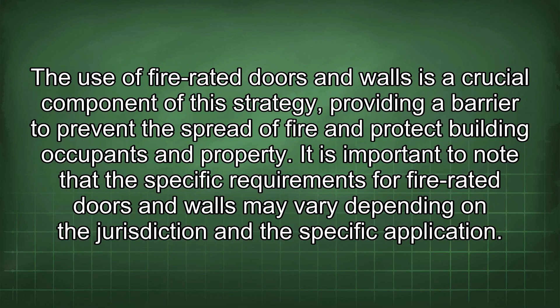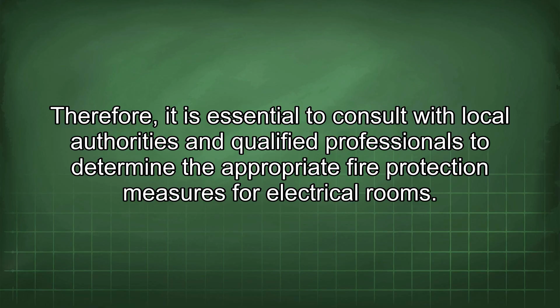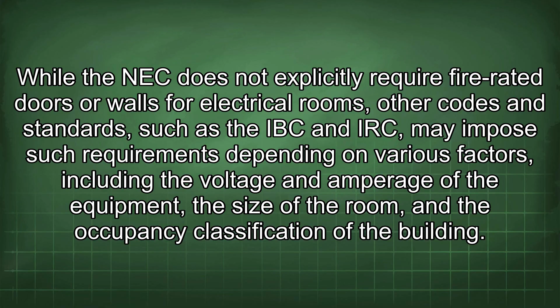It is important to note that the specific requirements for fire-rated doors and walls may vary depending on the jurisdiction and the specific application. Therefore, it is essential to consult with local authorities and qualified professionals to determine the appropriate fire protection measures for electrical rooms. While the NEC does not explicitly require fire-rated doors or walls for electrical rooms, other codes and standards such as the IBC and IRC may impose such requirements depending on various factors, including the voltage and amperage of the equipment, the size of the room, and the occupancy classification of the building.